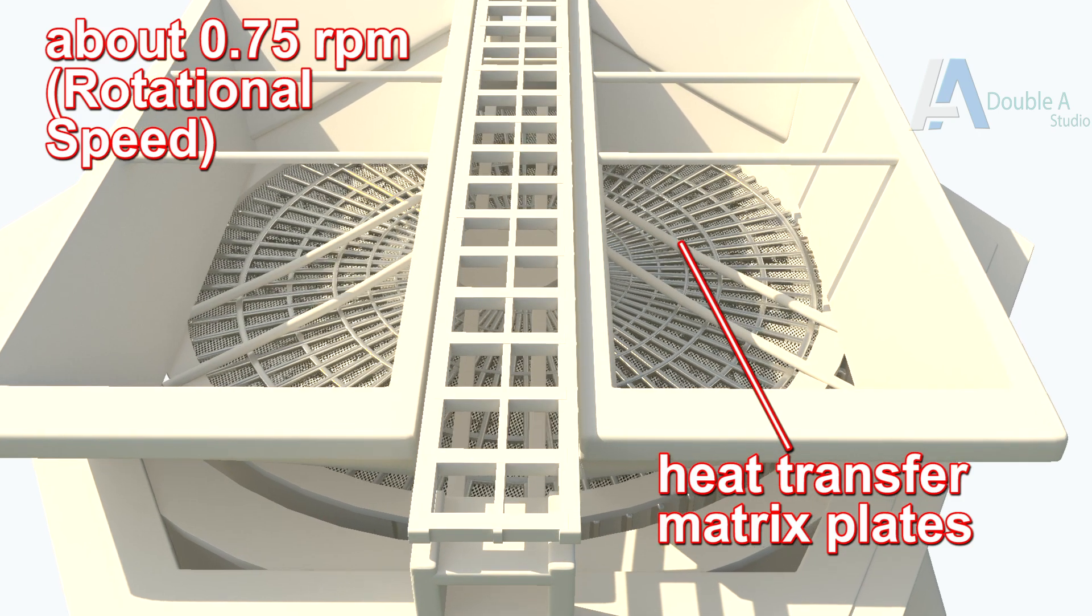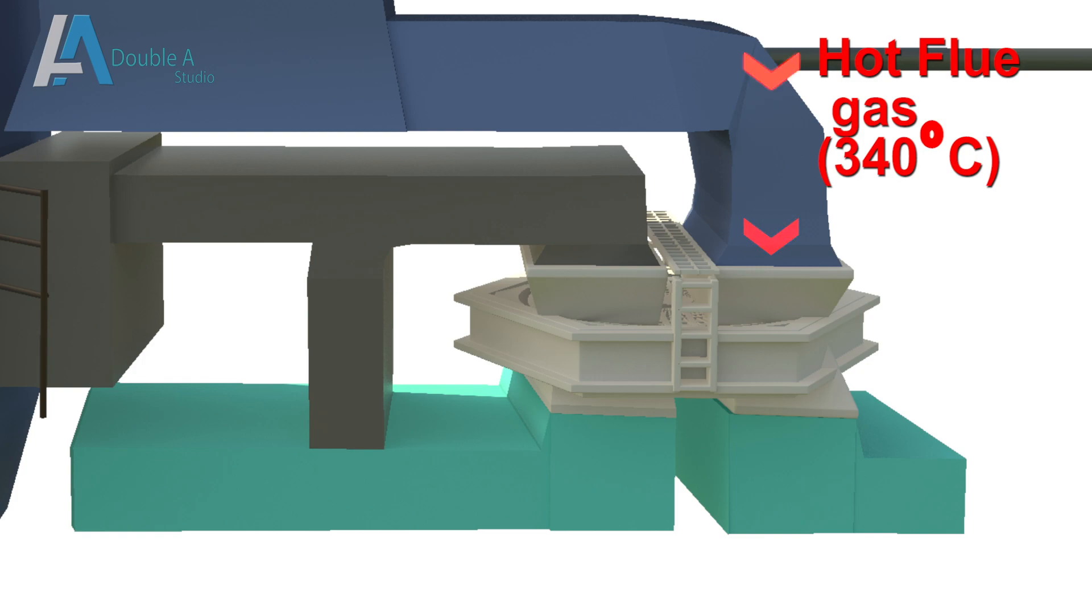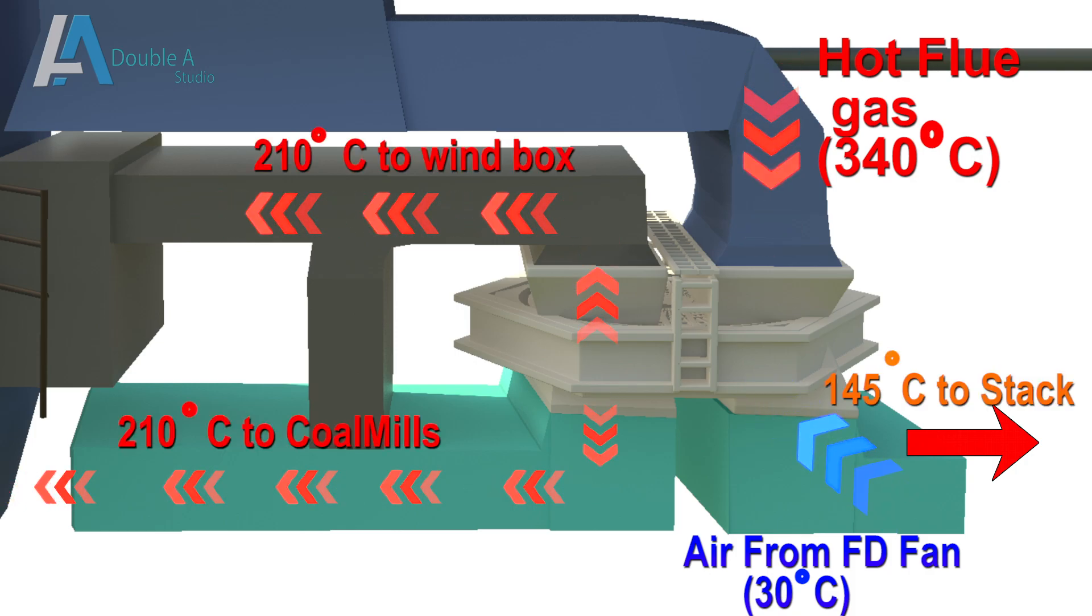When hot flue gas enters air preheater inlet duct at about 340 degrees centigrade, forced draft fans force ambient air of 30 degrees from other side of air preheater. During rotation, heat transfer takes place from flue gas to ambient air and temperature of air and flue gas comes to 210 degrees and 145 degrees centigrade respectively. However, there is an optimum value, about 140 degree of heat drop in flue gas to prevent corrosion.